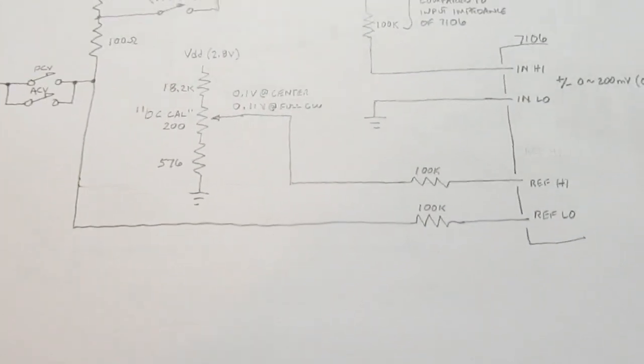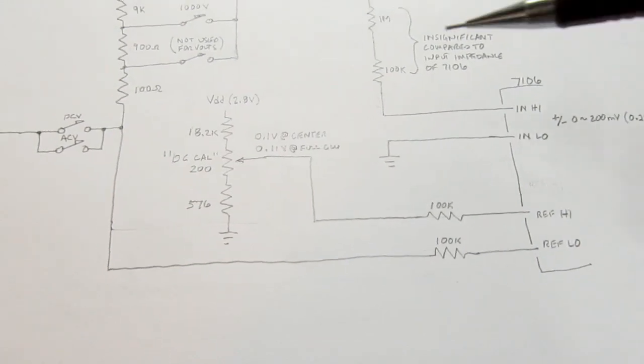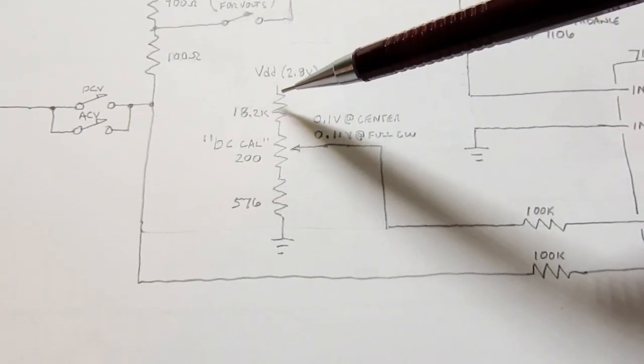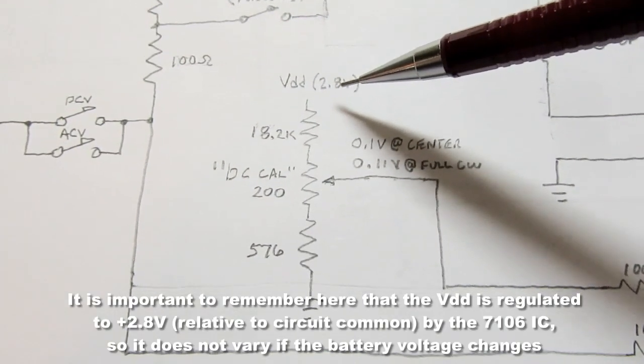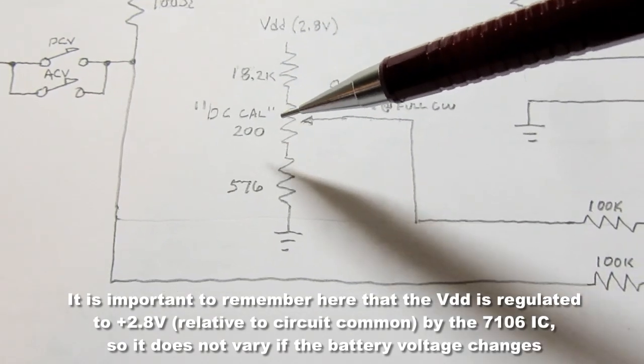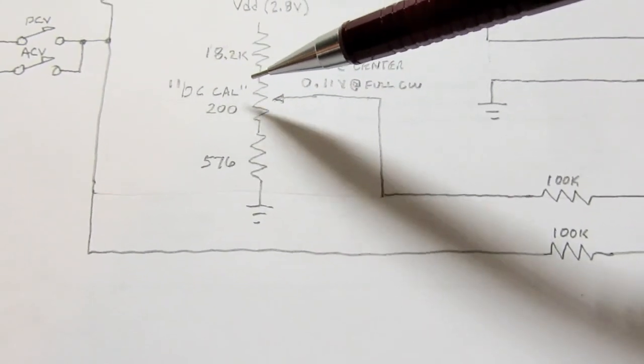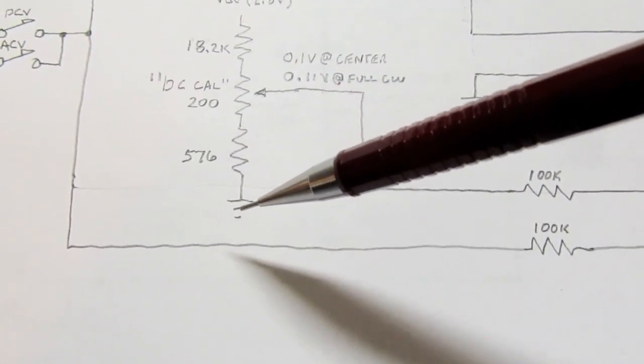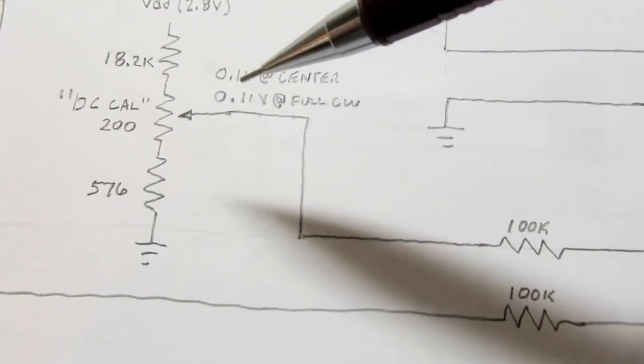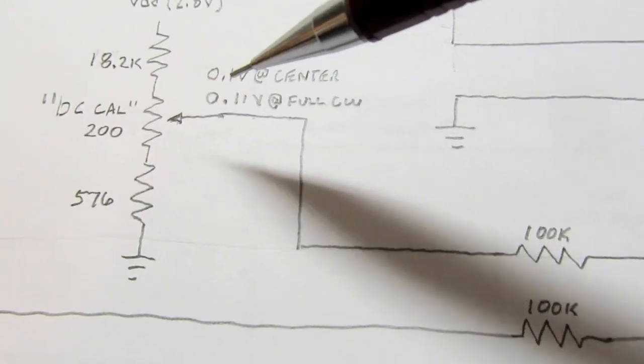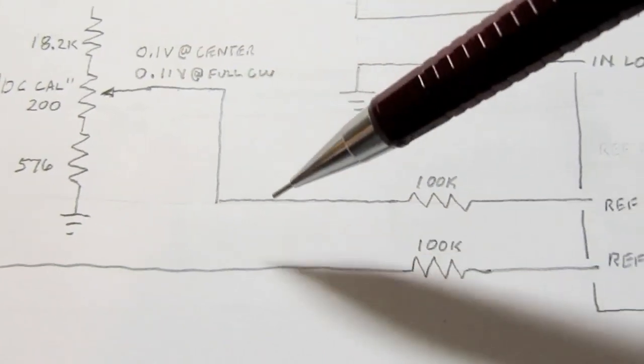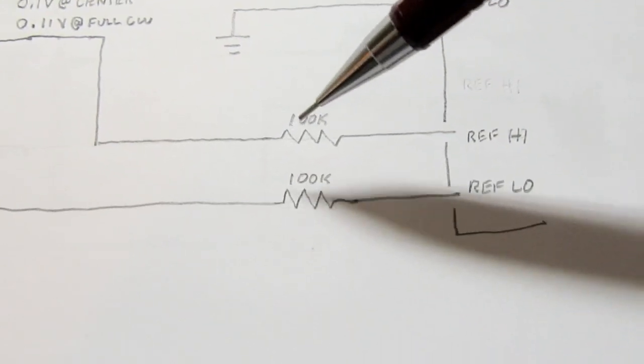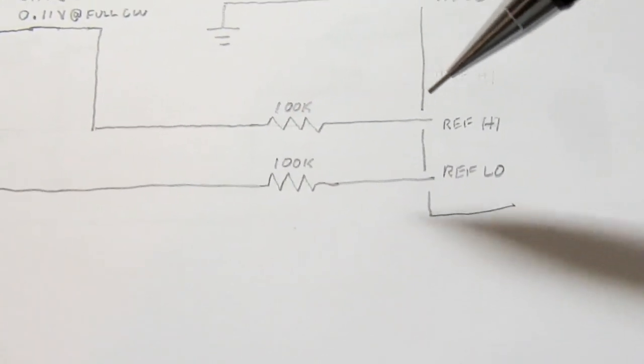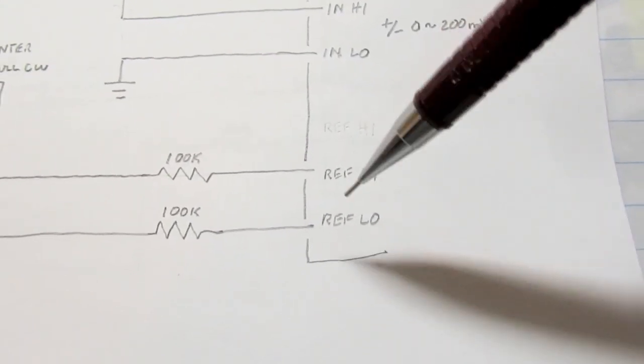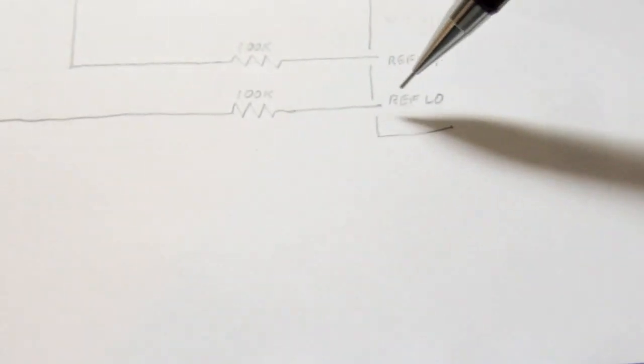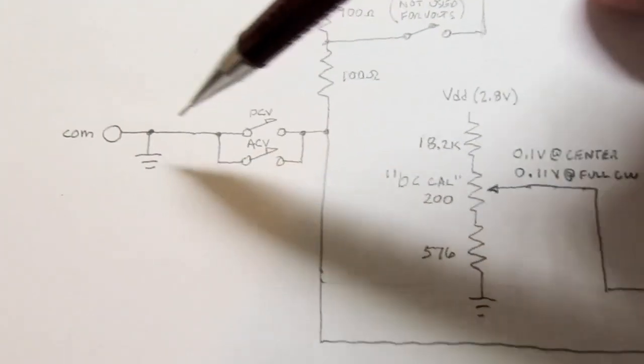What about the reference input? Those are important. Well, there's a resistor voltage divider between the VDD, or plus 2.8 volt signal. It's an 18.2K, then a 200 ohm trim pot, which is the DC calibration, and then a 576 ohm and back to circuit common. This is set up so that when the pot is in mid-range, you get 0.1 volts, and that's applied to the reference high. Again, there's these 100Ks in series, but they're not even there as far as the 7106 is concerned, because its own impedance is so much higher. And then the reference low just makes its way back, essentially to common.